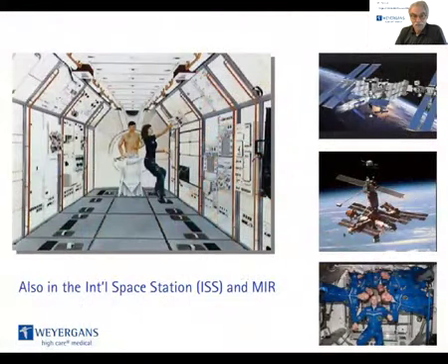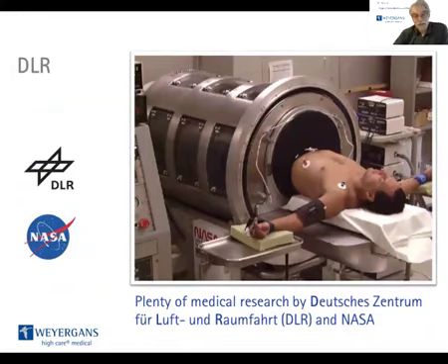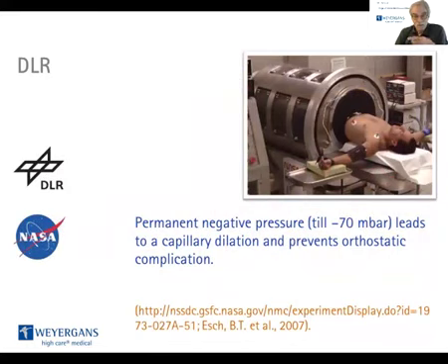Such an LBNP device is also required for the ISS. It was also part of the Russian MIR project. There is plenty of medical research around the LBNP device, done at the German DLR and at NASA. The most important outcome of that research is that permanent negative pressure, down to minus 70 millibar, leads to capillary dilation and thereby prevents orthostatic complications.